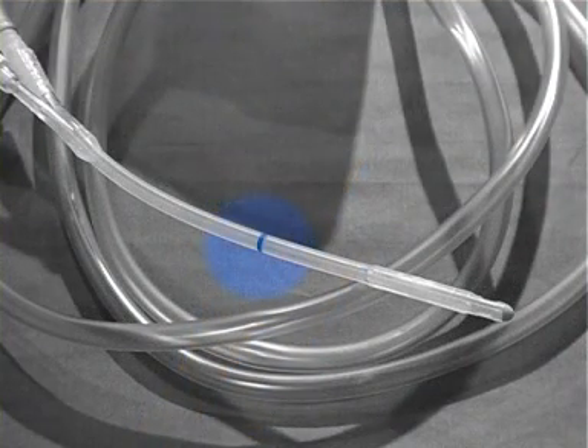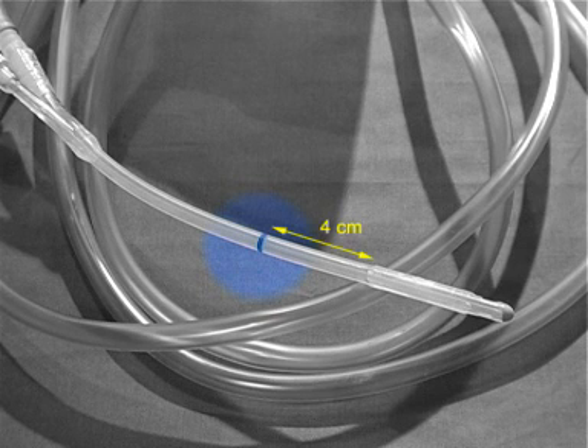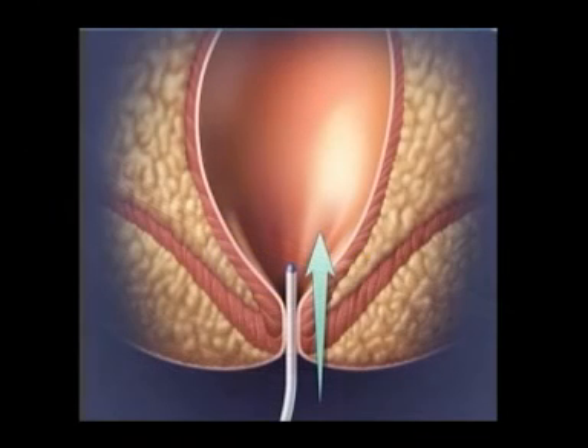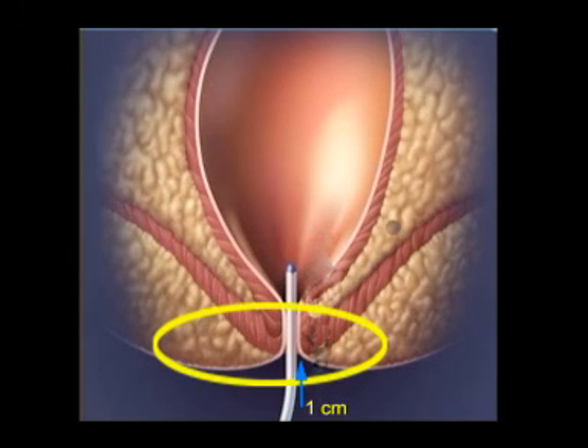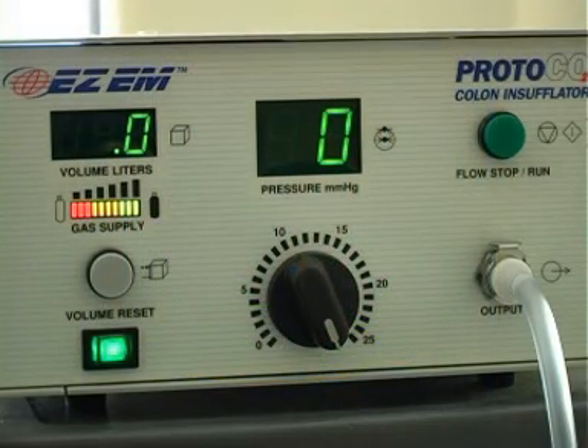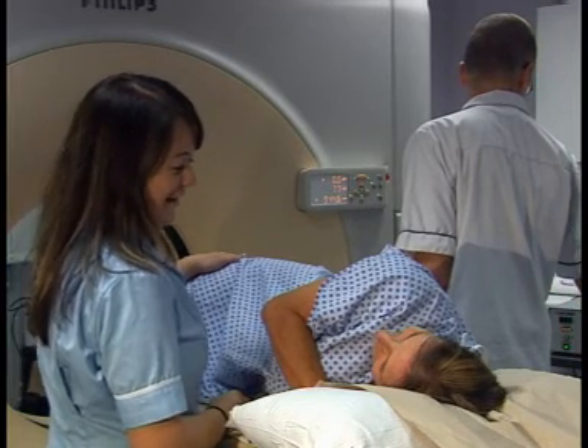There is a blue mark on the tube which is located 4 centimeters below the lower limit of the balloon, which corresponds to the approximate length of the anal canal. To ensure the entire balloon is appropriately placed in the distal rectum prior to inflation, this blue line should not be visible. The catheter should be inserted so that the blue line lies within the distal canal, approximately 1 centimeter from the anal opening. The automated insufflation machine is designed to be used with carbon dioxide, although air can be used. Once the catheter is safely inserted, the green start button is pressed to start insufflation.